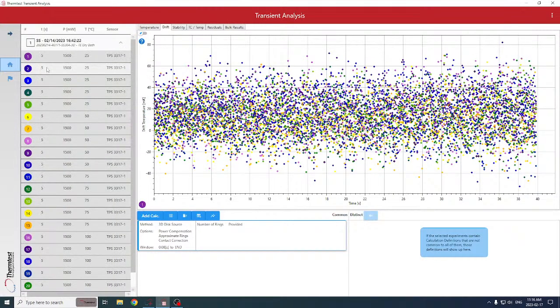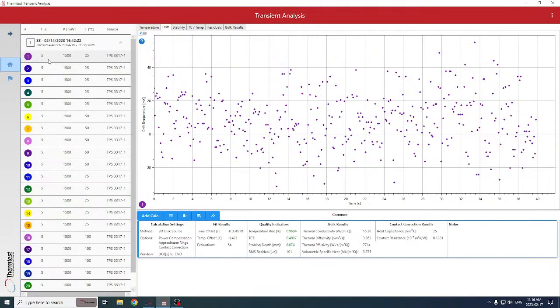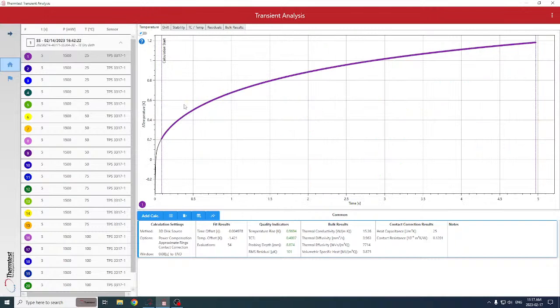So in advance of every measurement, drift monitoring is done to ensure that our temperature is stable. If we had a decaying shape, then that means your sample is still cooling. And the reverse of that, if you had a warming shape, that means your sample is still heating. So that could come from, if the temperature unit or even your room is not stable, you would see those shapes. And it's a warning to say, hey, allow more time in between measurements of the same sample, or allow more time for your temperature to become stable. And then, as always, we can see our temperature rise versus time, which is our raw data.